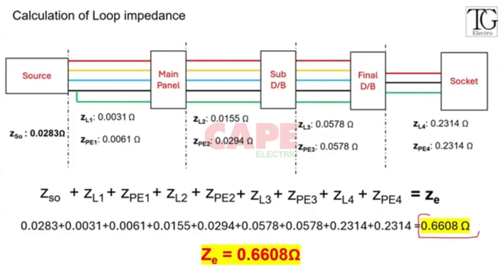I have added all those and I'm getting a value of 0.6608 ohm. This is the calculated impedance at the socket outlet. If you take a loop impedance meter from Sonel or Fluke, go to this socket, plug in that meter and run the fault loop impedance measurement, you are supposed to get a value of 0.6608. But you might not get that exact value, because if you add reactance to this formula you will get a variation of around 2 to 5 percent. So you should get close to this value.